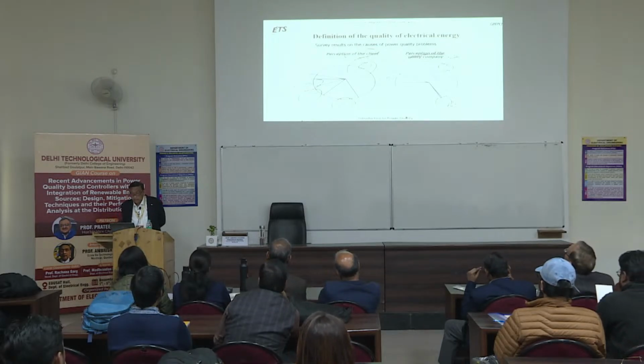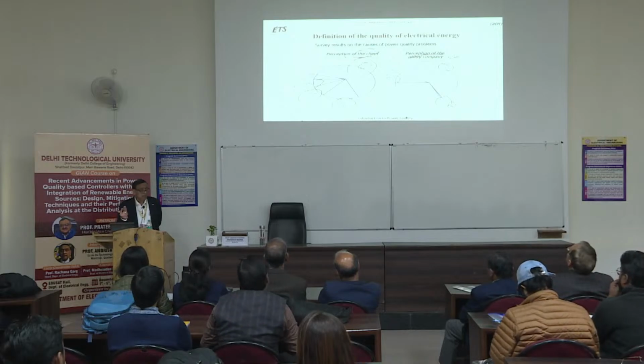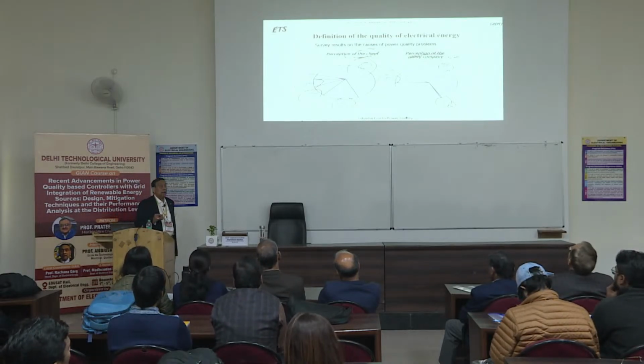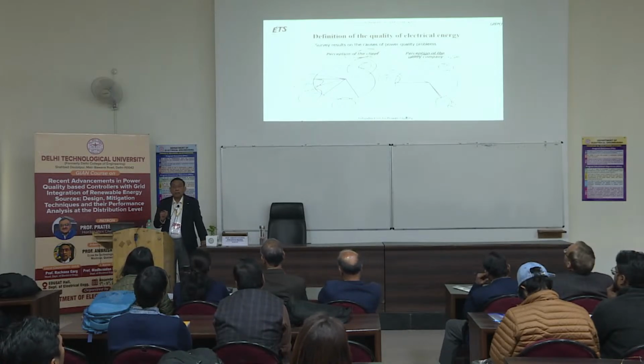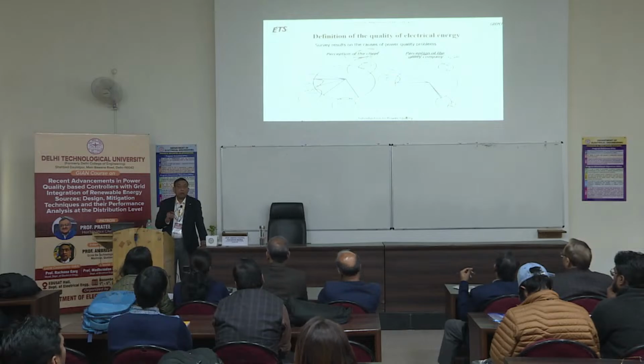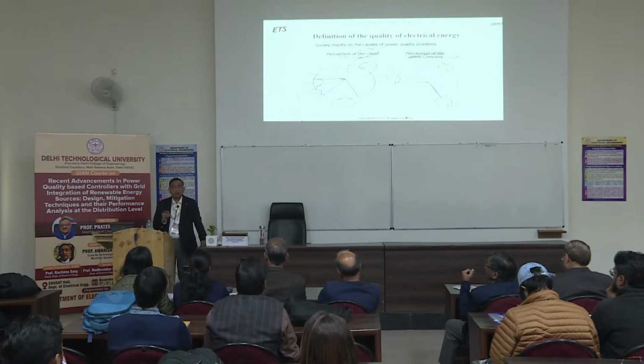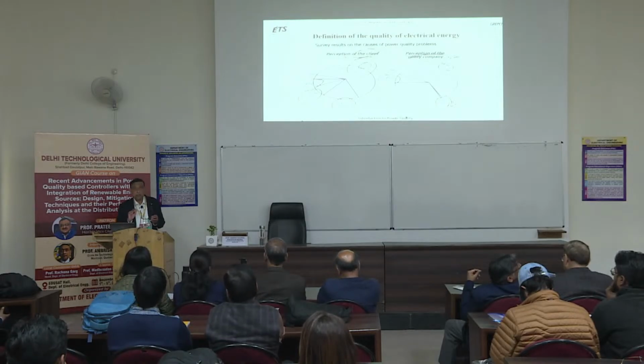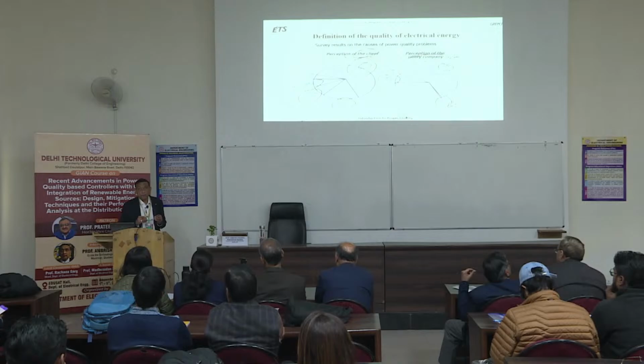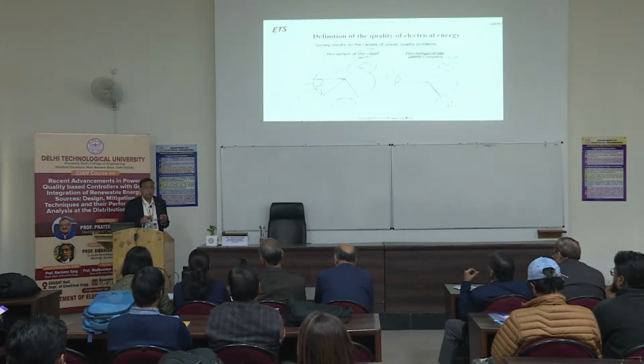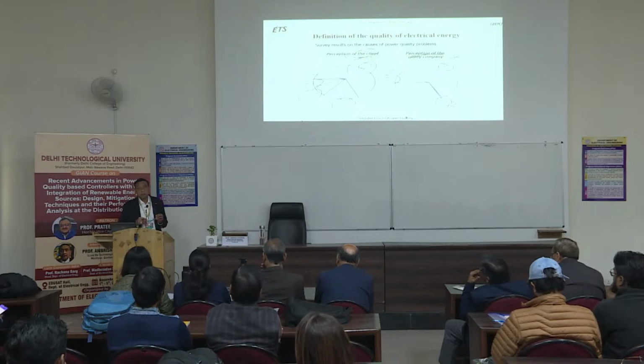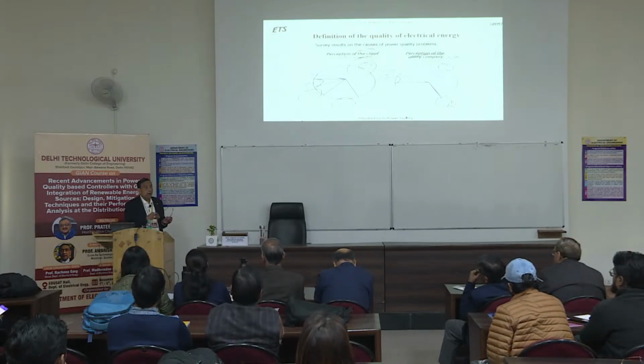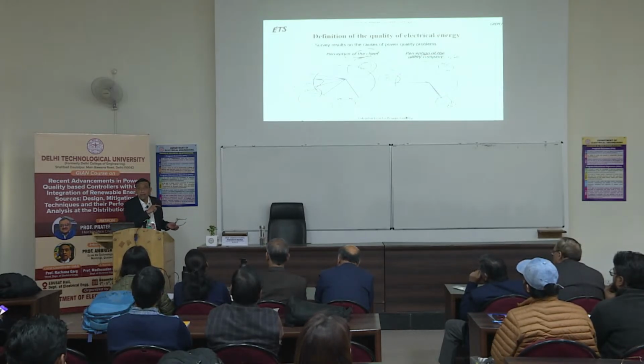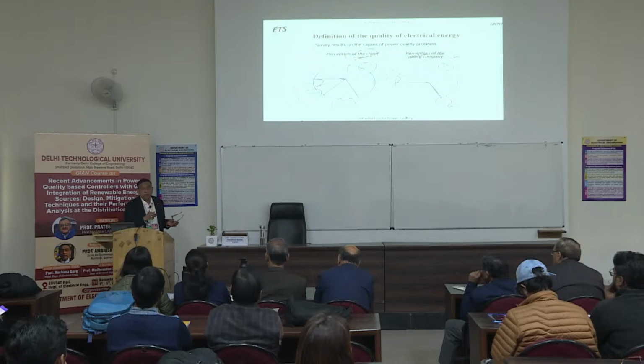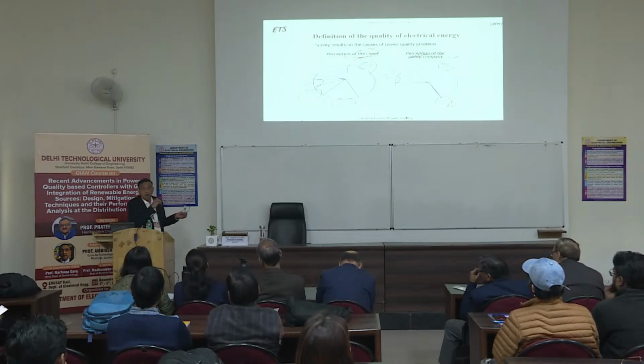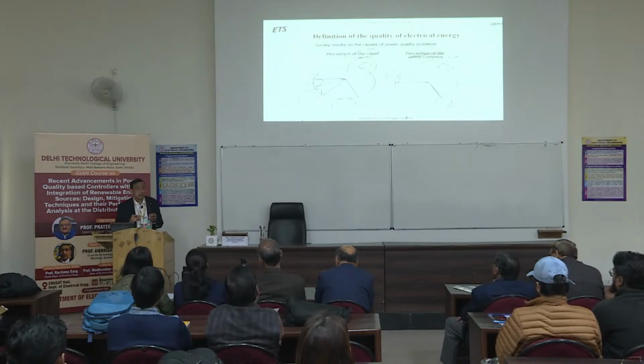Neighbors, 8%, according to the clients. What can the neighbors cause? Sometimes what happens, there is one client which has a linear load with reactive power, and it has put a capacitor bank at the entry of the industry to improve the power factor. But there is another neighbor, some industry nearby, which is generating harmonics. So those harmonics are attracted by the capacitor bank of the earlier client. Those harmonics will come and they will heat up, and sometimes they may burn the capacitor bank of another client. So this is what happens, problems caused by the neighbors.